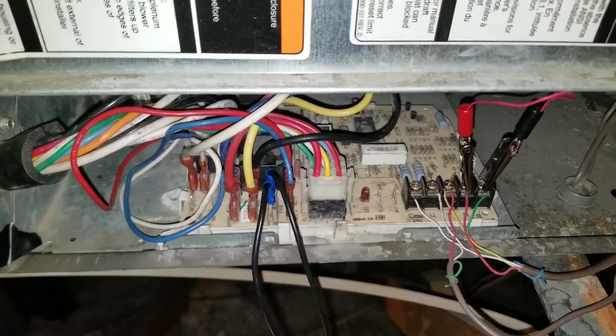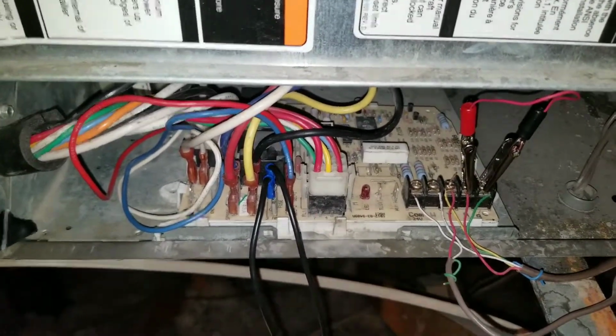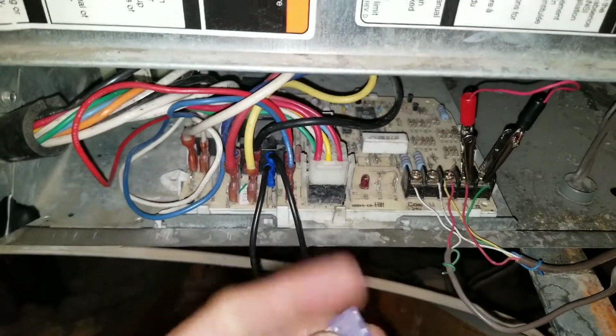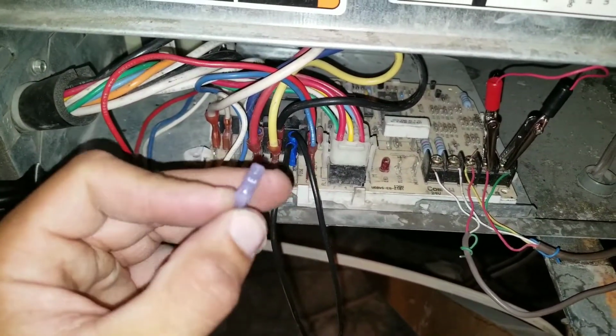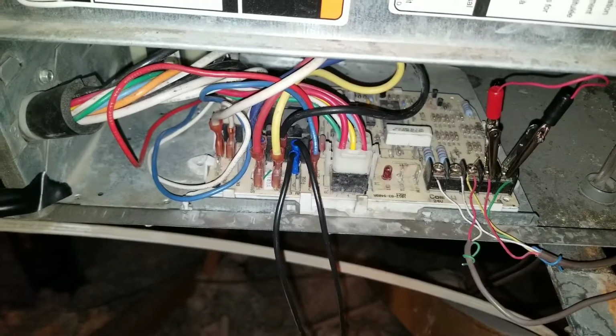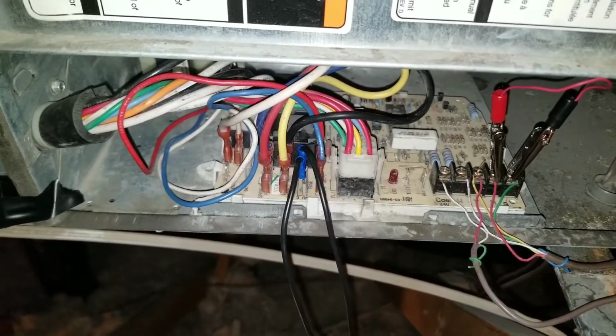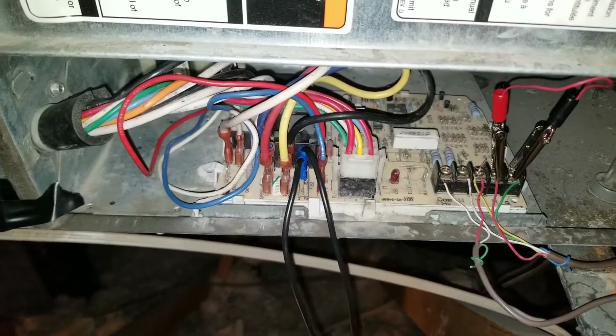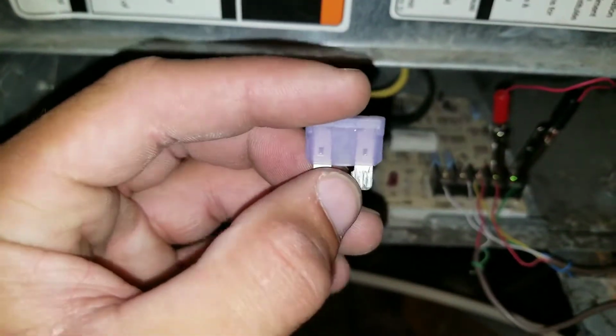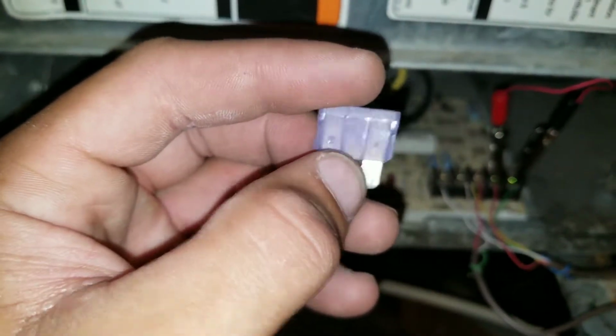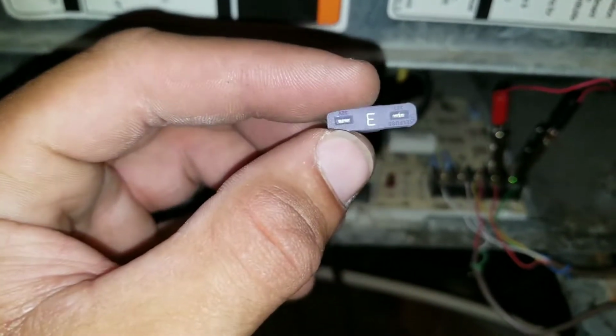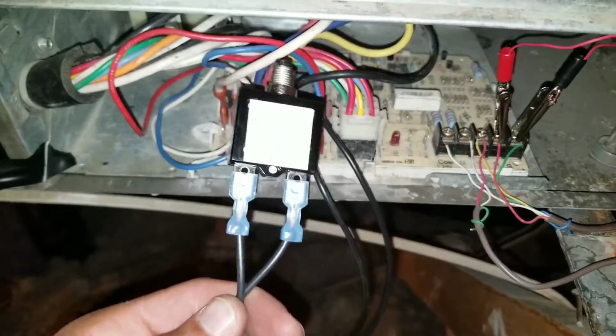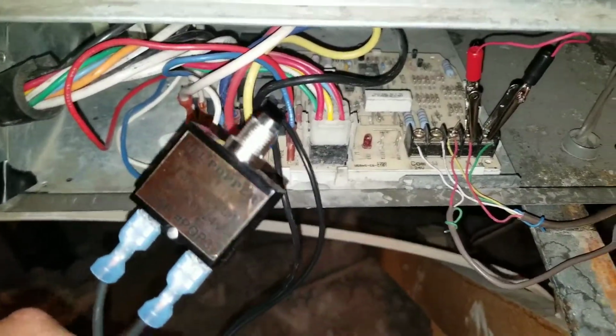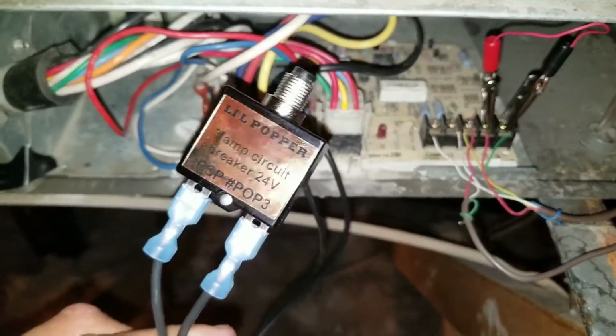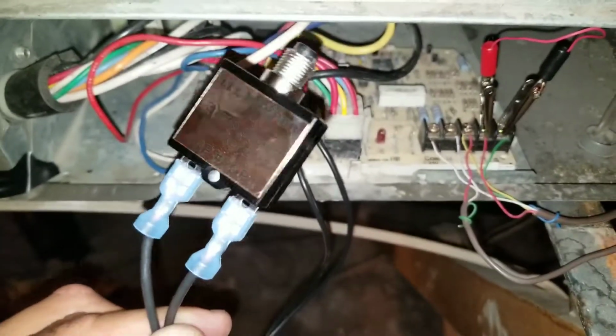Now what happens oftentimes when you have an issue with a low voltage short, you can see here this is the fuse. The fuse is what ties into your furnace board, and a lot of times you'll find that when you have a low voltage short, if it's in your blower, your heat, or in your condensing system, you'll come back and your fuse will have the link in the middle broken, and you'll see some discoloration due to it popping. I've purchased what's called a resettable fuse, and basically instead of just replacing fuse after fuse trying to troubleshoot the system, what this does is it actually will pop and allow me to reset it without me having to replace the fuse.